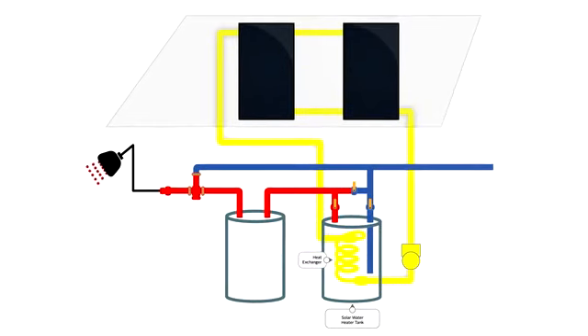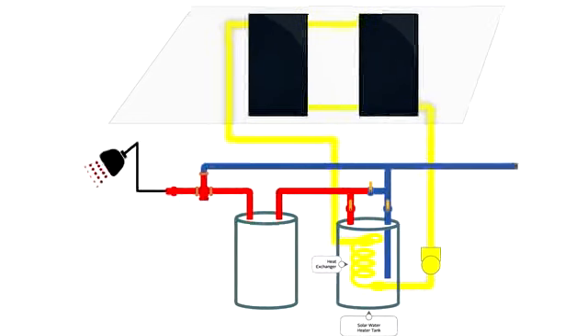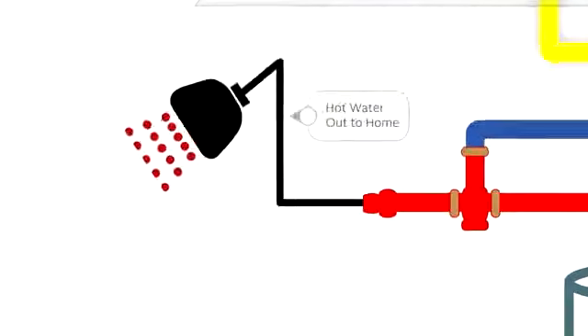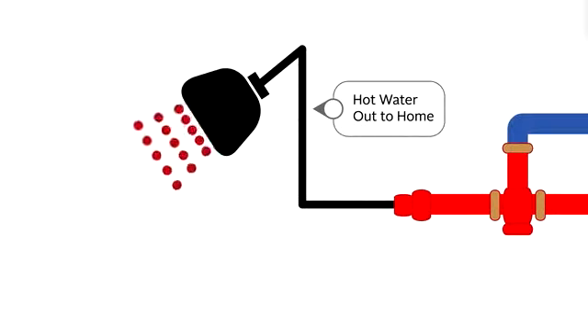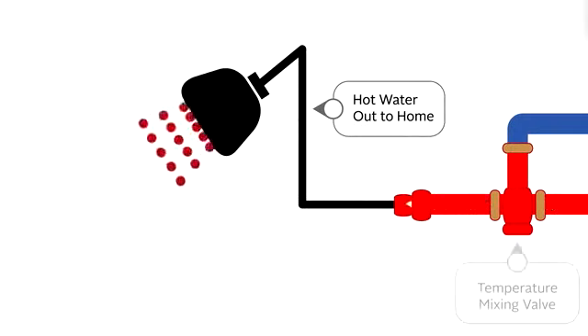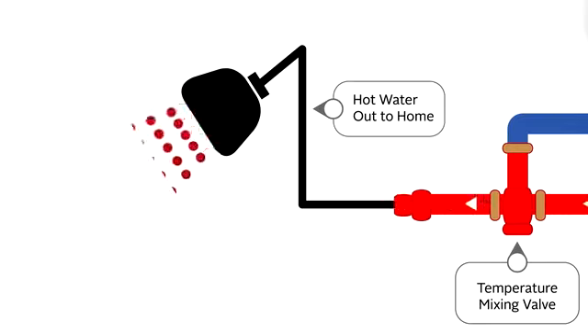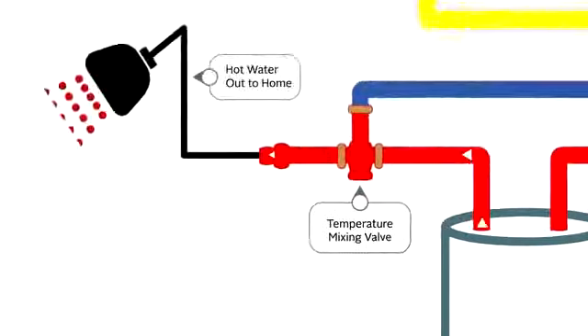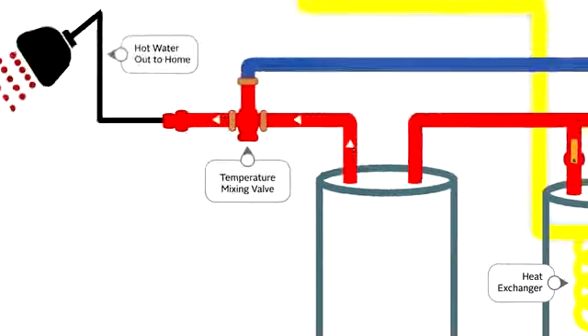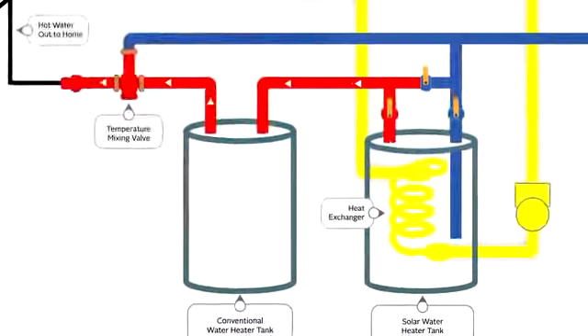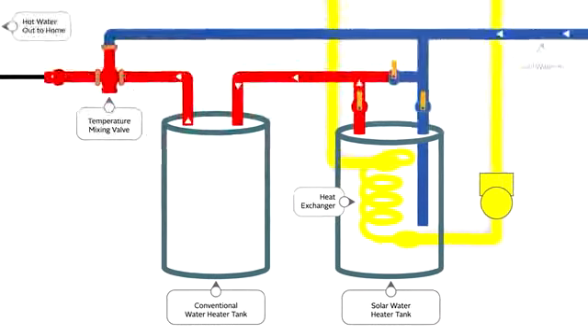When you use hot water in your home, it's drawn from your conventional water heater tank and is replenished by the stored hot water from the solar water heater tank. A mixing valve adds cold water if needed to ensure that the hot water is always delivered at a safe temperature.